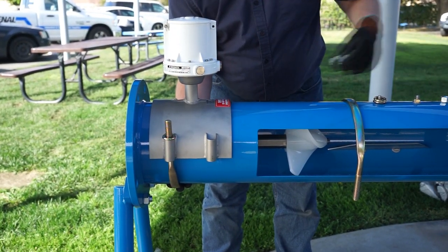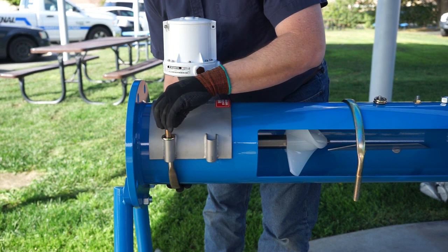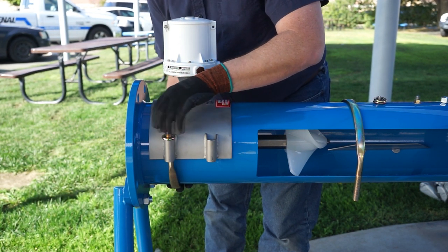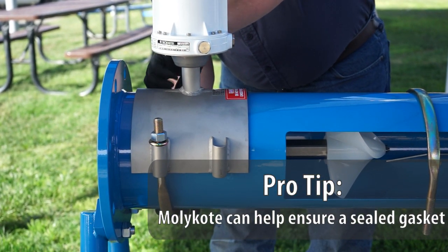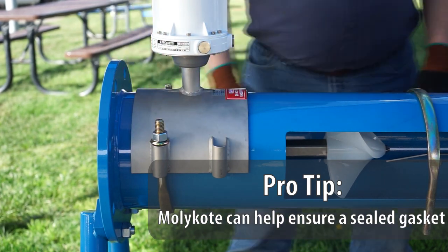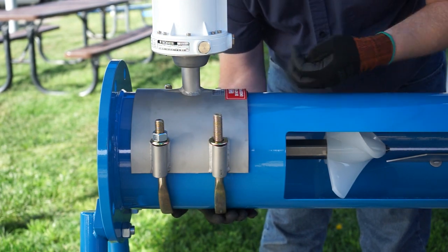Right now we just want to make sure that when you tighten the bolts in by hand, you're getting an even thread. Now repeat that with your second U-bolt. A pro tip here: using a generous amount of Molykote or an equivalent lubricant on the gasket helps ensure a solid seal of the gasket and saddle to the pipe. It acts as both a lubricant and a sealant, and we recommend it.